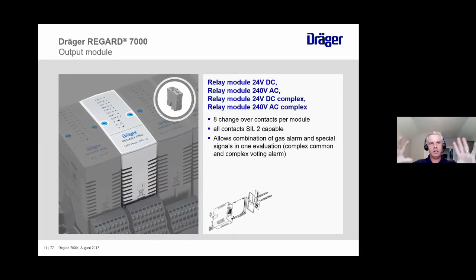This is a situation that's happened. That's why we developed the complex relay module. Let's say that you have 4 different points, and you want to make sure that each of those points is in alarm before you'll trip some mitigation action, either turning on a fan or opening an overhead door or some big action that you're taking based on all 4 of those points going into alarm. Let's say that you have a situation where one of the sensors attached to that relay module goes into fault, but the other 3 go into alarm.